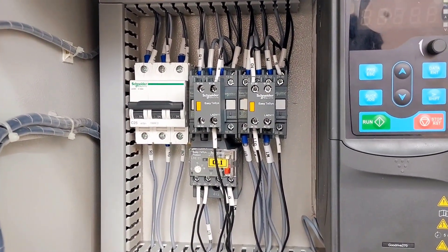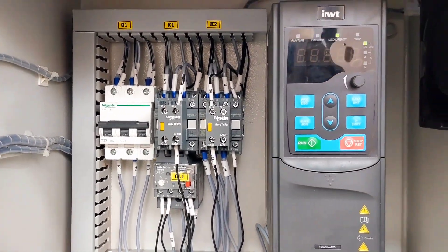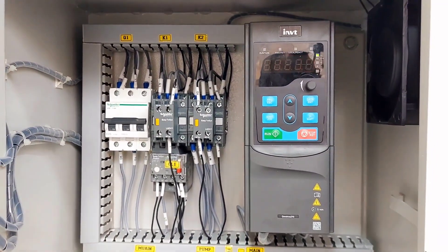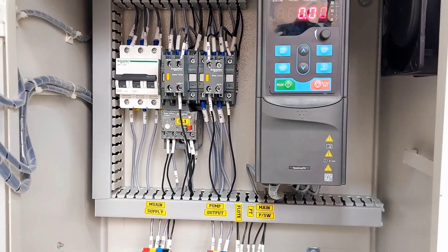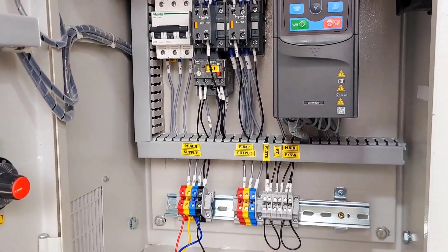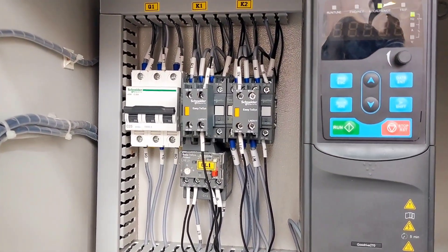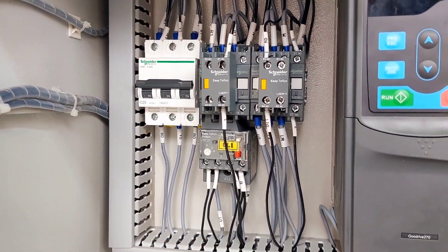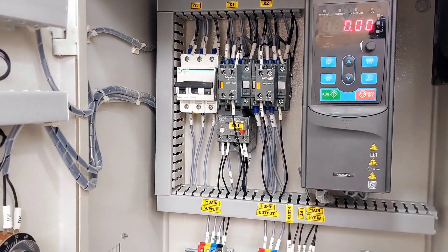I can show you inside. Here we have provided mains 3-phase MCB, an INVT drive with a fan to reduce heat and humidity inside the panel, and Schneider make contactors and Schneider make thermal overload relay, provided for when we operate the pump in manual mode.